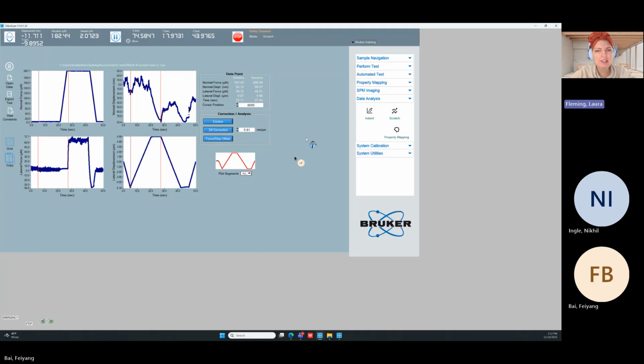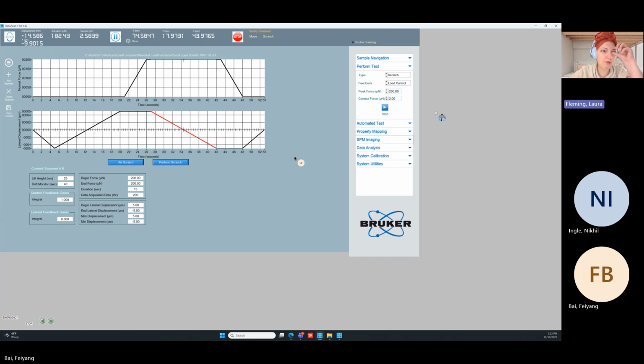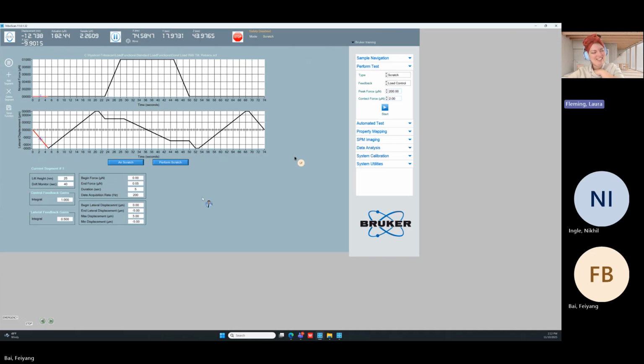Yeah. Okay, let's go back to the Perform Test tab. And I want you to go to the hamburger menu. Standard load functions. Constant load with tilt retrace. Ooh. So, yeah, exactly. Weirder, right? Hopefully the beginning looks a little bit familiar. So here, 0 normal force for that first 20 some seconds. As we pull back, then trace along the sample surface where our scratch will be. Where people get confused is these little steps in. But really, you know, we look at this and basically we're still at 0 micronewtons. So it traces and then it comes back just like a little bit. Then it loads into the sample and then it performs a scratch.